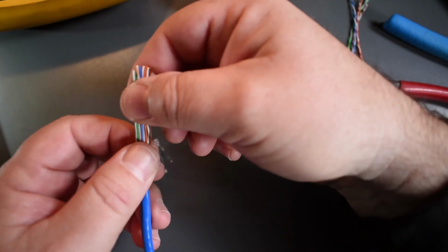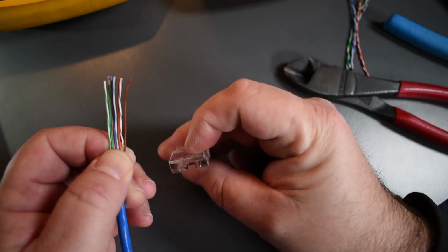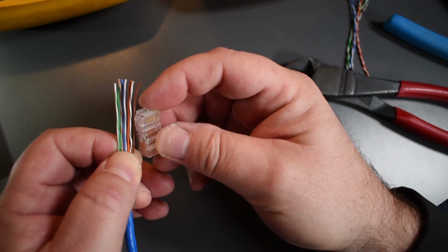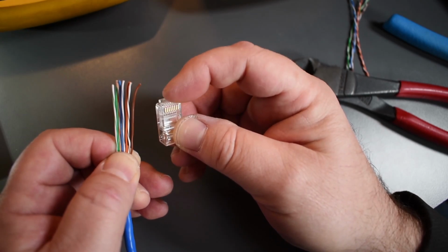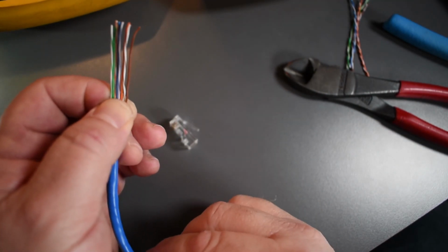So now we're going to have to pre-cut this again. Now before we pre-cut that, I want to point something out to you. Those conductors have to go right to the very top here, hit the wall. So that means they have to be nicely, equally cut. That's why you make sure the cable is straight, because if you have it bent, you cut it straight, you straighten it out, and they come out different lengths. The other thing is here, and maybe I can show it under the microscope. Yeah, let me not forget this time. There's a little pinching clip here. Right here, it's this guy right here.